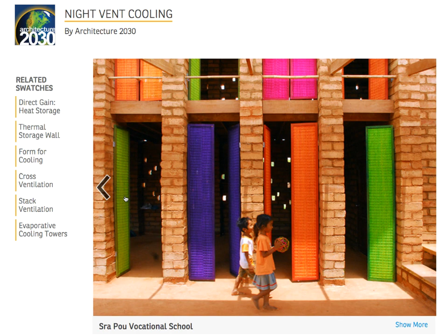Then when the outside temperature gets cool enough, and we usually define that by it's cooler than the top of the comfort zone, or it's cooler than the mass temperature, then we're going to open the building. Typically that's going to be about 10 o'clock at night, say in a climate like Knoxville, or maybe midnight in a climate like Albuquerque, where it's hotter during the day. It's going to take that long for the outside temperature to get cool enough. Then we ventilate at a relatively high rate of airflow for however many hours we have available to us when the air is cool. That cools down the mass.